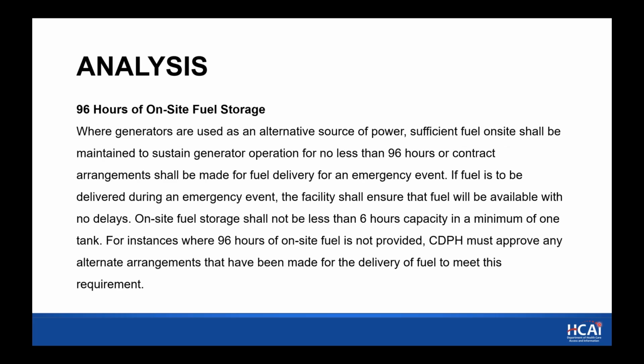So the 96 hours of on-site fuel storage, the bill specifically states that where generators are used as an alternate source of power, sufficient fuel on-site shall be maintained to sustain generator operation for no less than 96 hours, or contract arrangements shall be made for fuel delivery for an emergency event. If fuel is to be delivered during an emergency event, the facility shall ensure that fuel will be available with no delays. That's the direct quote from the bill.